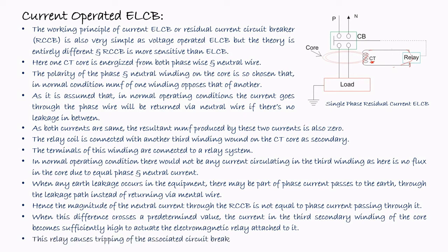And this relay causes a tripping of the associated circuit breaker to disconnect the power supply to the equipment. So this is the concept of the current operated ELCB. In normal condition, when the current is flowing from phase, it will pass to the load and the same current will return to the neutral line. So the current in the phase line and the neutral line will be equal. So no current will flow through the CT, so the relay will not be activated.